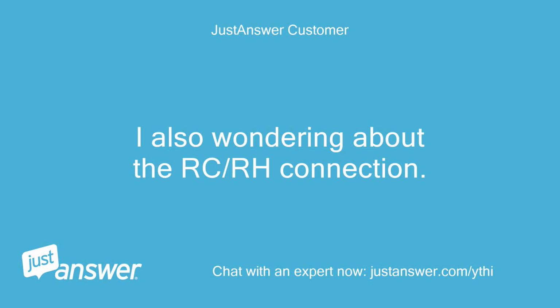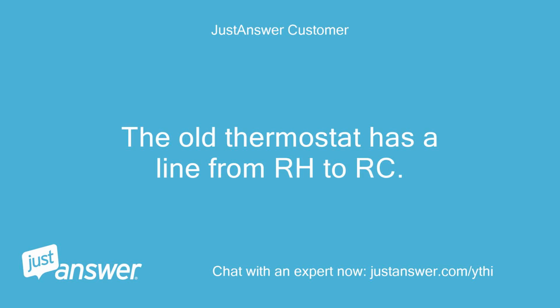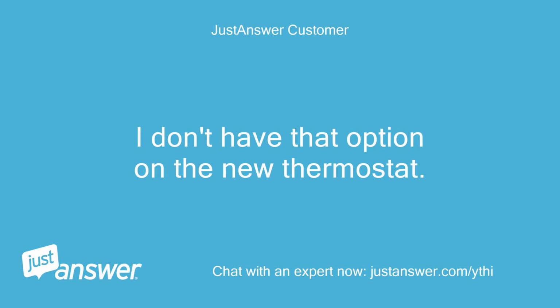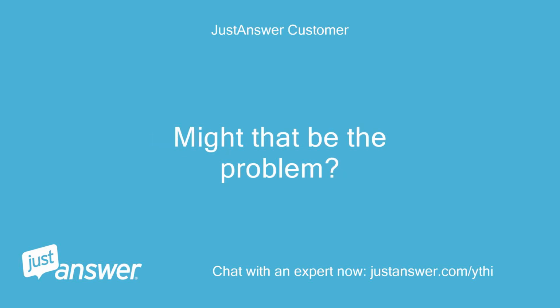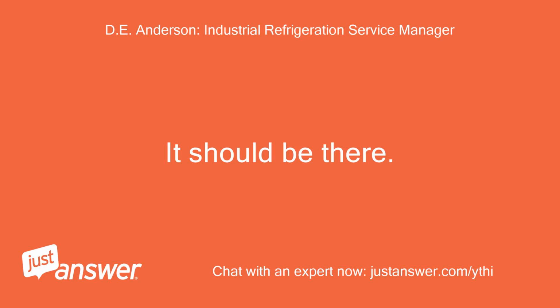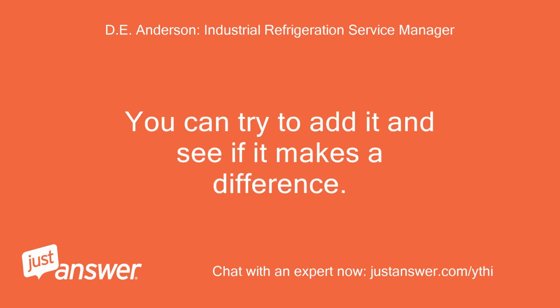I'm also wondering about the RC/RH connection. The old thermostat has a line from RH to RC. I don't have that option on the new thermostat. Might that be the problem? It should be there. You can try to add it and see if it makes a difference.